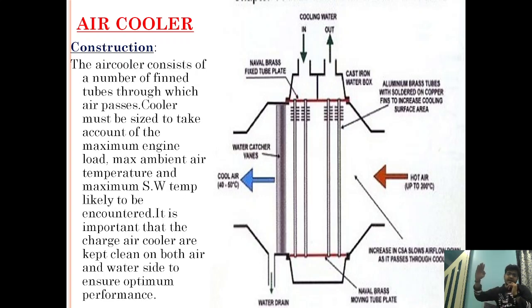The temperature gradient is very high, which will cause thermal shock. If the temperature of the cooling air coming from here is around 40 to 50 degrees Celsius, then the temperature gradient will be lower, and hence the thermal shock will be less.